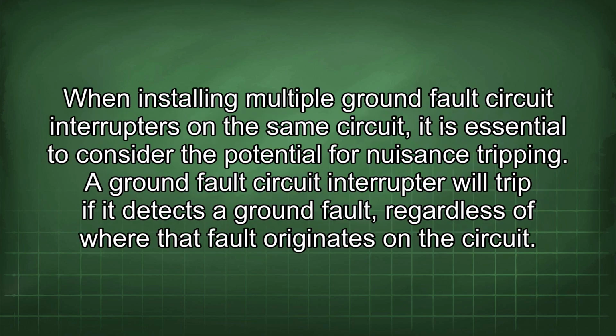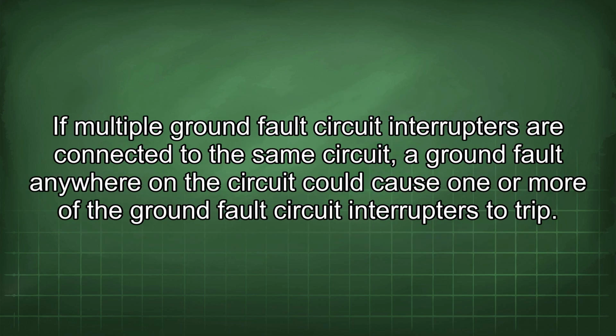When installing multiple ground fault circuit interrupters on the same circuit, it is essential to consider the potential for nuisance tripping. A ground fault circuit interrupter will trip if it detects a ground fault, regardless of where the fault originates on the circuit. If multiple ground fault circuit interrupters are connected to the same circuit, a ground fault anywhere on the circuit could cause one or more of the ground fault circuit interrupters to trip.